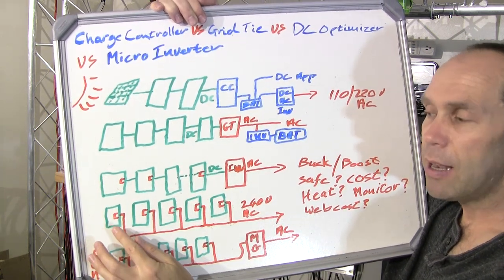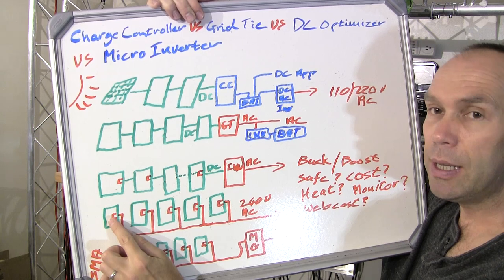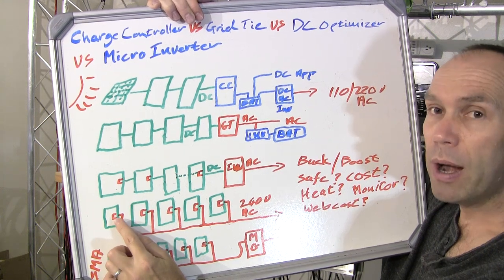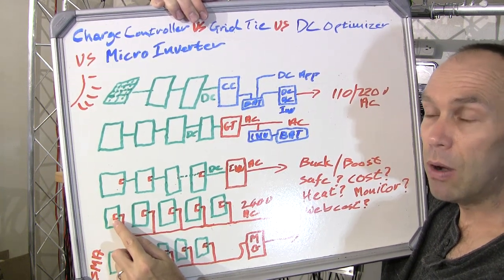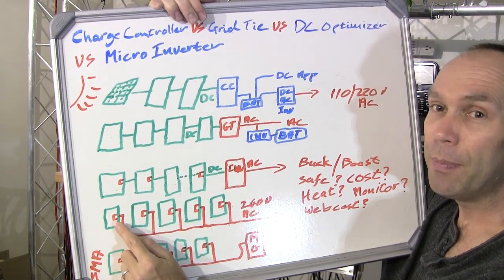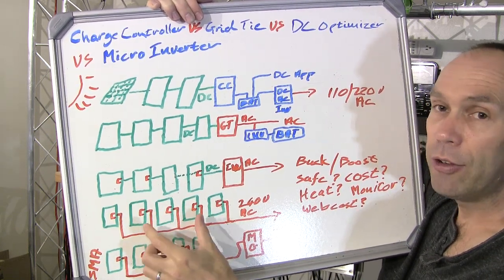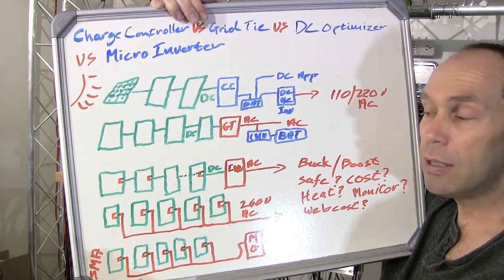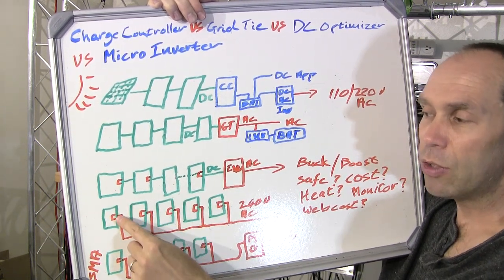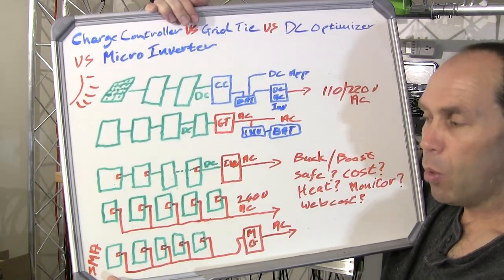Another issue in terms of failure points with micro inverter systems is that your solar panels are sitting in the sun and getting very hot. If you're doing full MPPT DC-to-DC conversion and then DC-to-AC conversion, those micro inverters are working and generating heat themselves, plus they're on the back of a hot solar panel. That potentially means a good reason for failure. They have to be very careful about the components they use — electrolytic capacitors will dry out, so they have to use other types of capacitors.